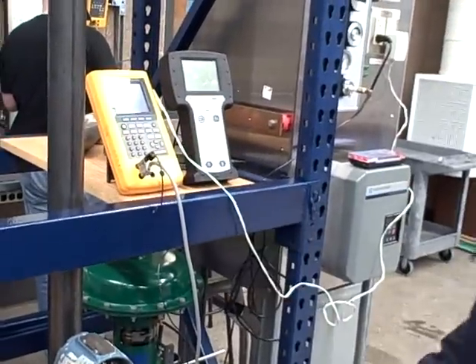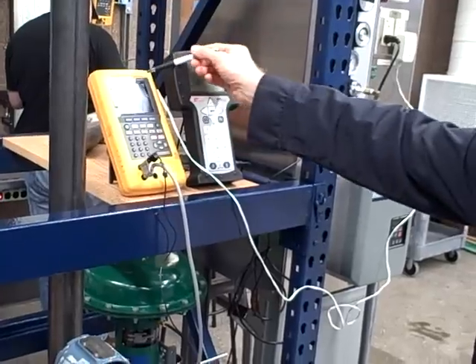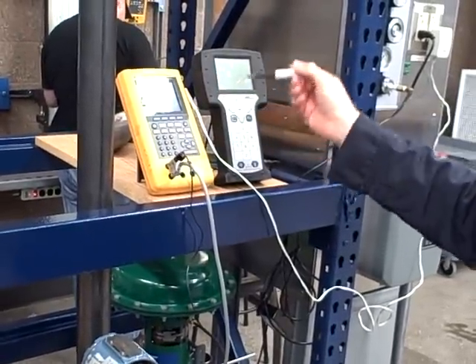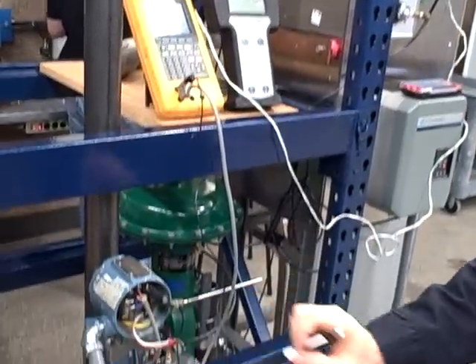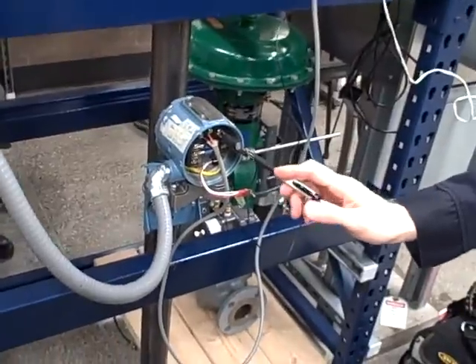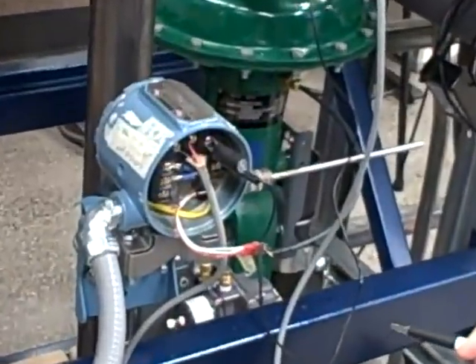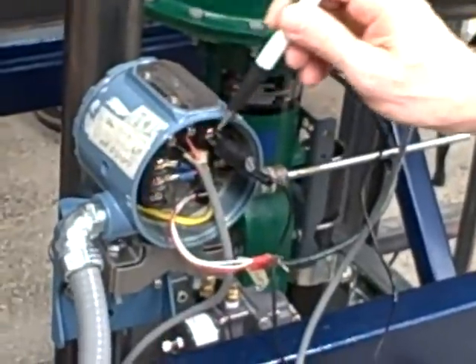We're going to set up a Fluke 744 Documenting Calibrator to simulate an RTD. Our transmitter is a Rosemount 3144 transmitter, and it's currently set up to take in a three-wire RTD signal.